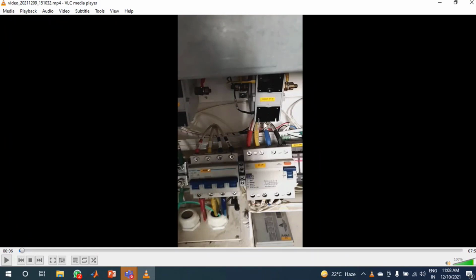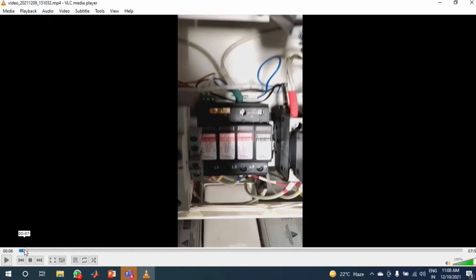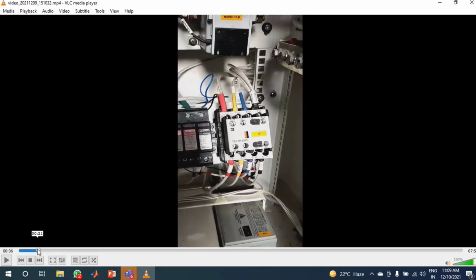This input supply is going to the relays. These are the protective relays in case of over voltage, under voltage, over frequency, under frequency - this will not take the power. So these are the relays that will take that. Now there is an auxiliary battery also in the charger. This auxiliary battery ensures that the relays operate properly and the sensors work properly for the charger also. This is the most important area, the SMPS.